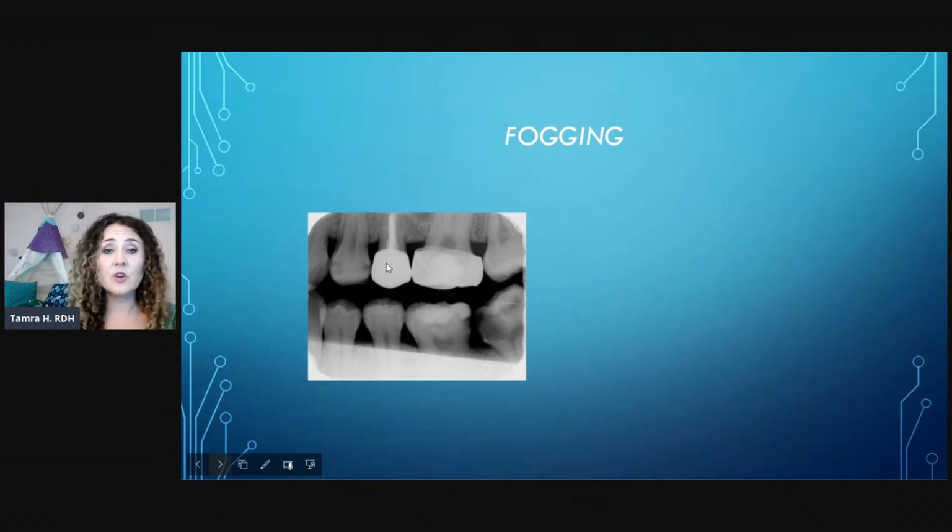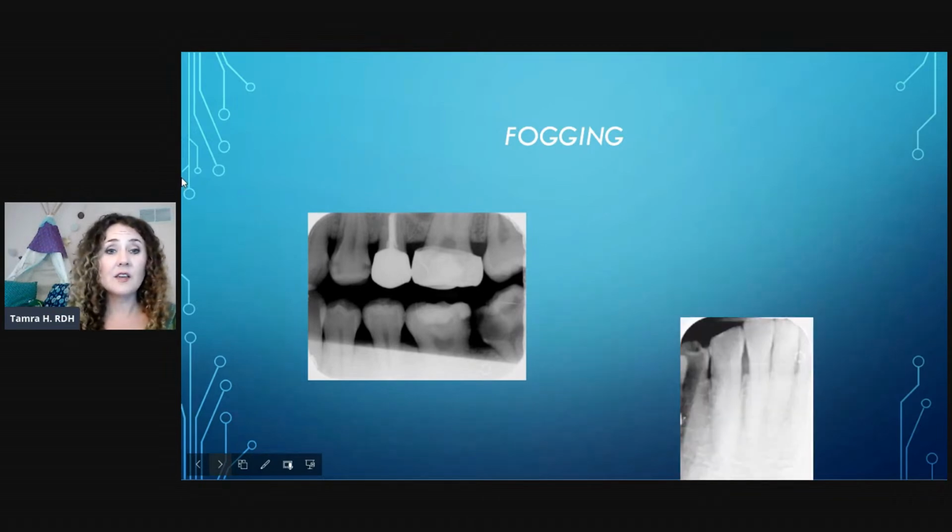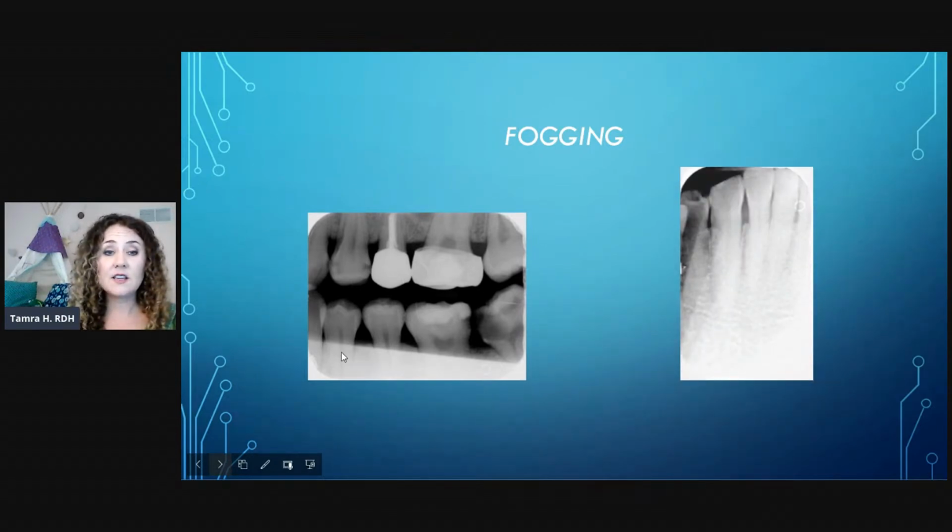But that's good. You're going to notice that that is fogging when you can actually see the outlines of the teeth and anatomy on the more radiopaque aspect of the film. So here, this image was in light for a considerable amount of time. We're starting to see that there is some total erasing that's happening of the actual images.